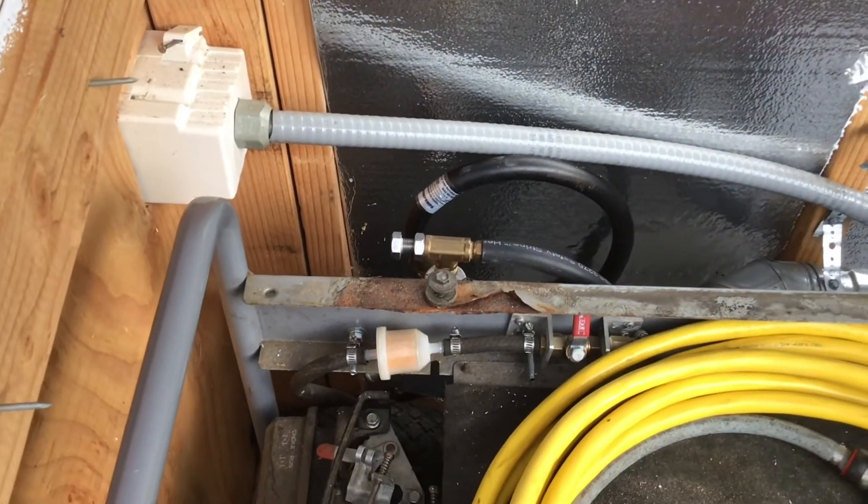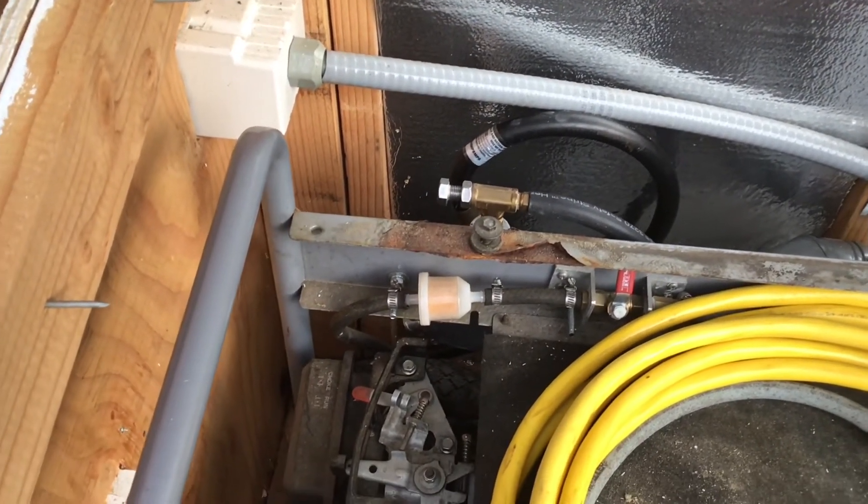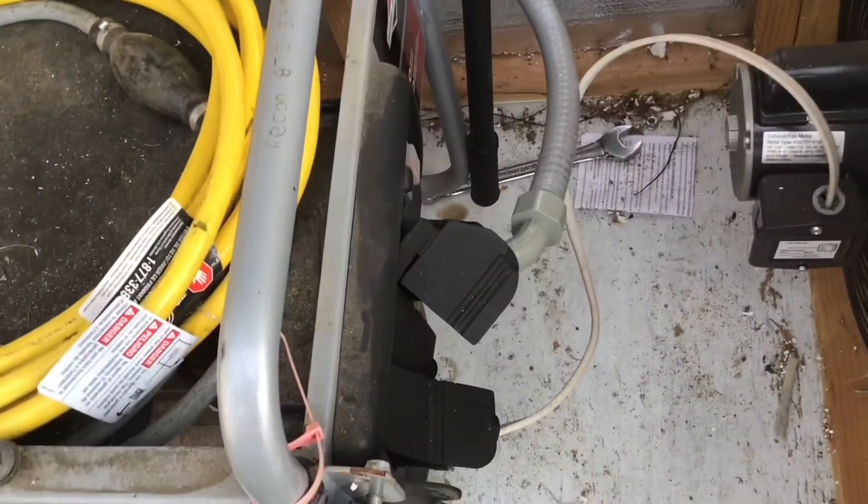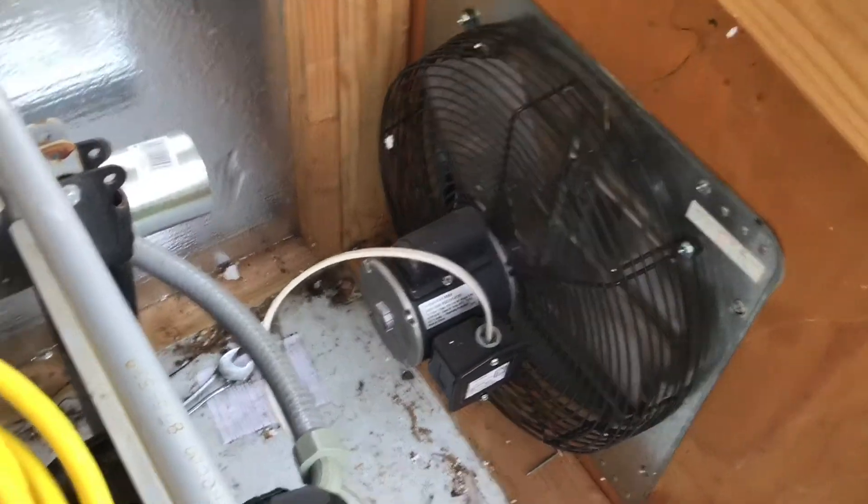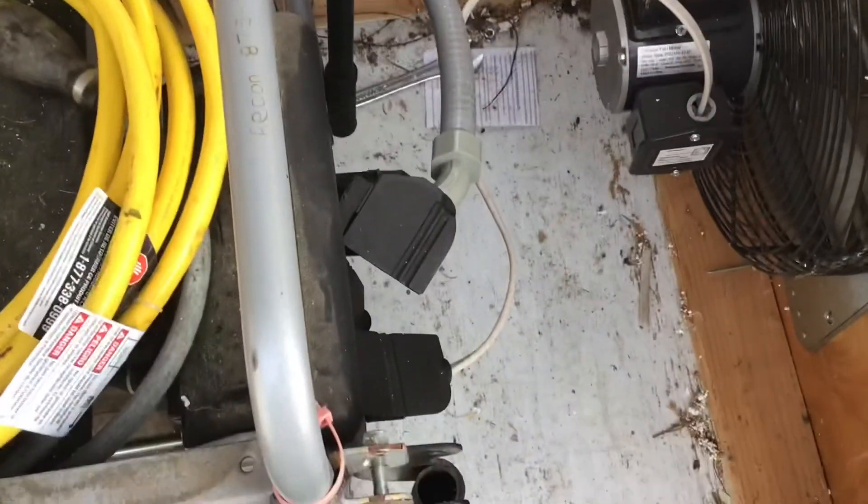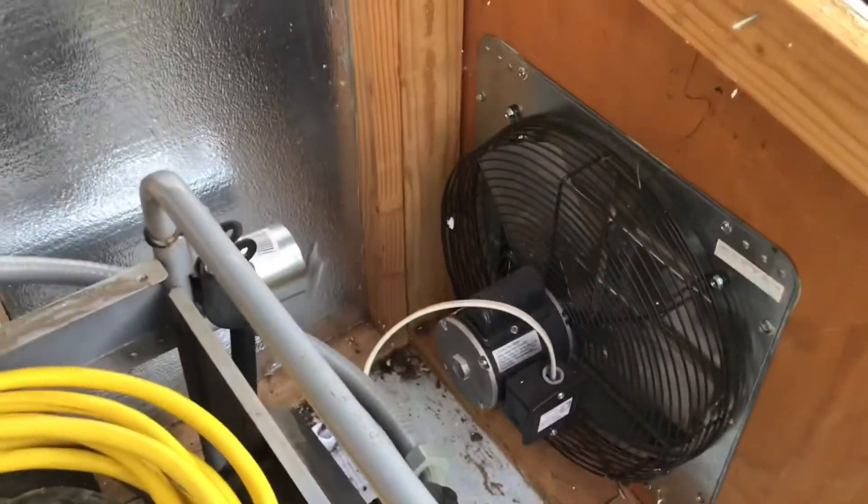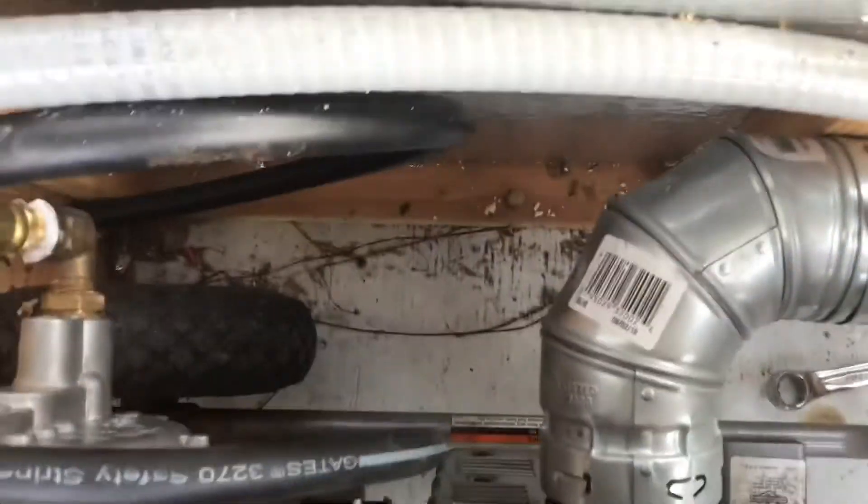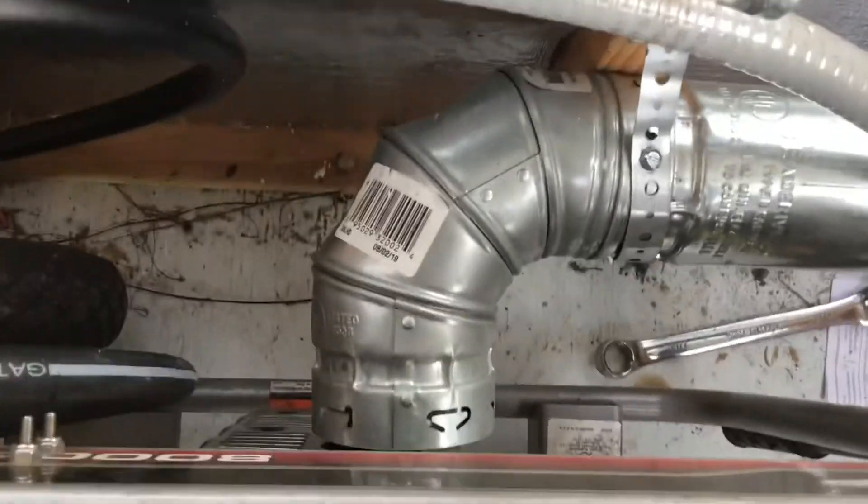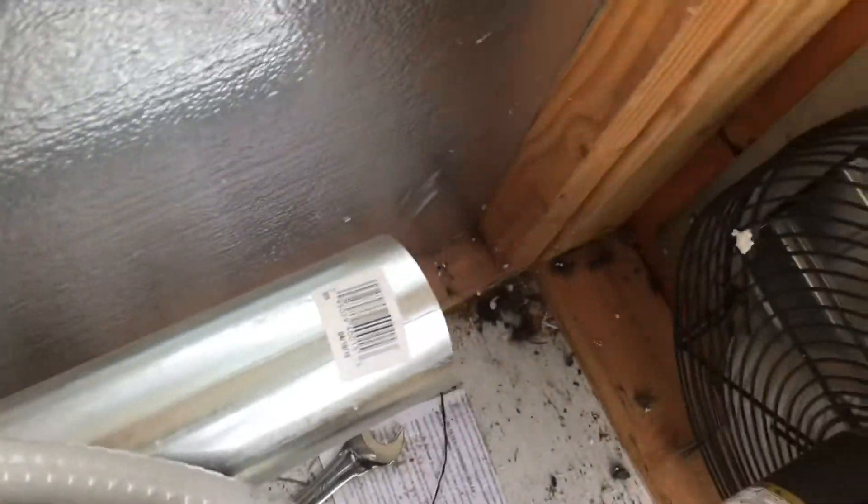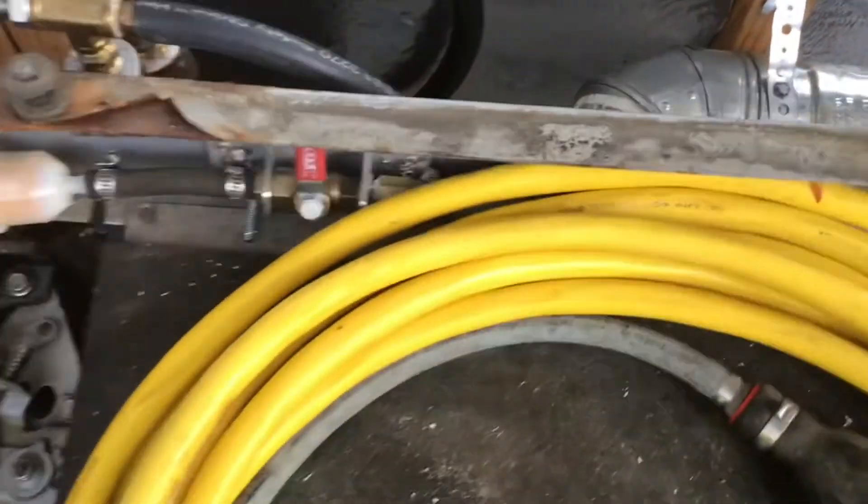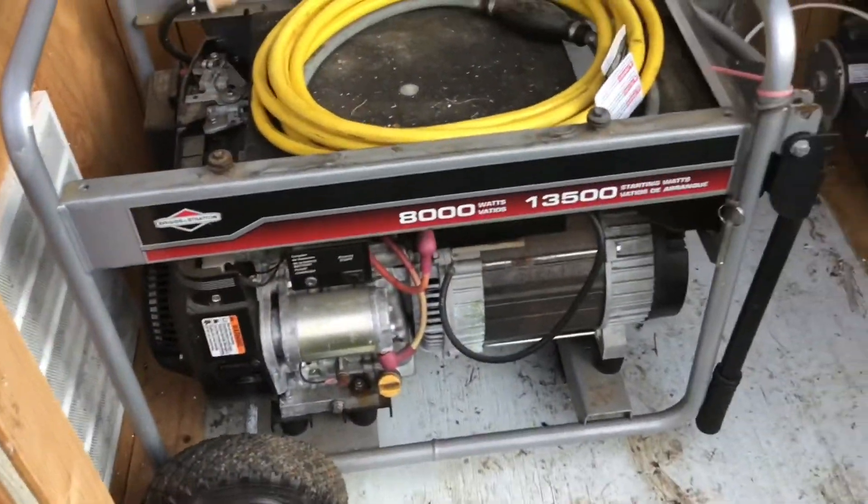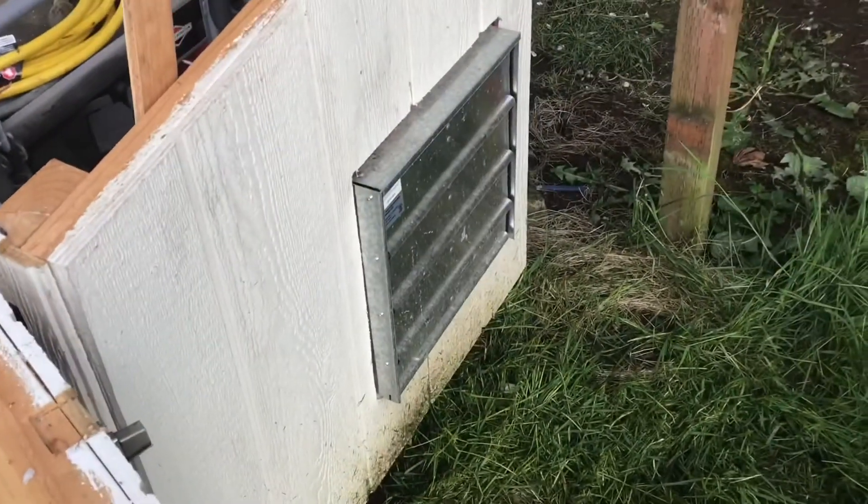You have to adjust that whether you're using natural gas or propane because they have different energy densities. You can see the cord running over here. It plugs into the generator. Over here, you can see an exhaust fan plugged into the generator as well. So that comes on automatically as soon as I fire up the generator. For exhaust, I have this triple wall pipe here, turning an elbow and exiting in front of the fan. It actually works really well. It keeps the wall cool, gets the exhaust gases out. And on the outside, I just have an automatic louver cover.